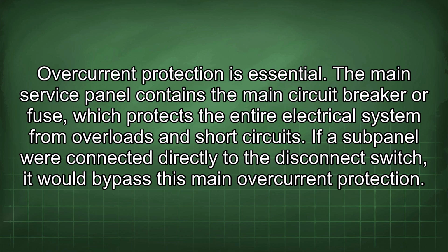Overcurrent protection is essential. The main service panel contains the main circuit breaker or fuse, which protects the entire electrical system from overloads and short circuits. If a subpanel were connected directly to the disconnect switch, it would bypass this main overcurrent protection.